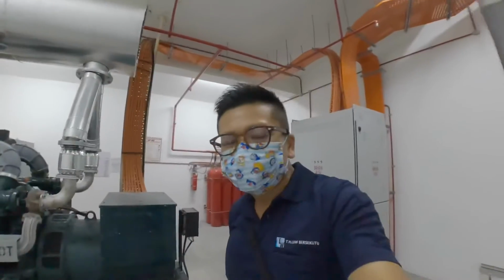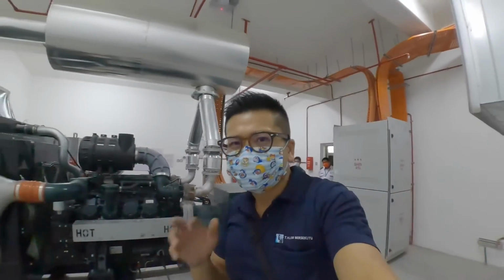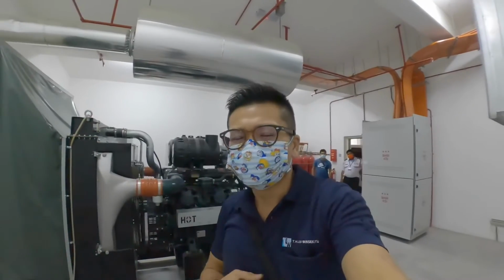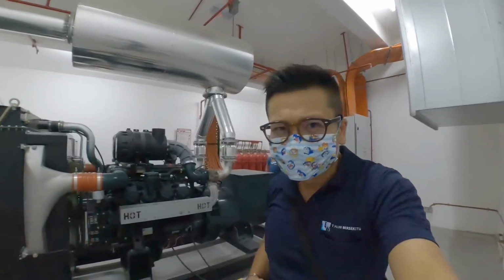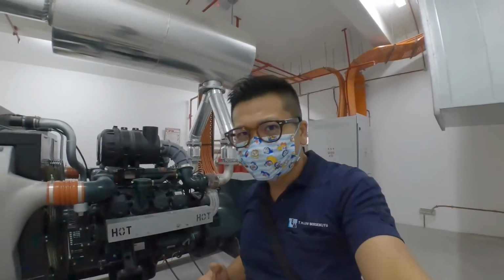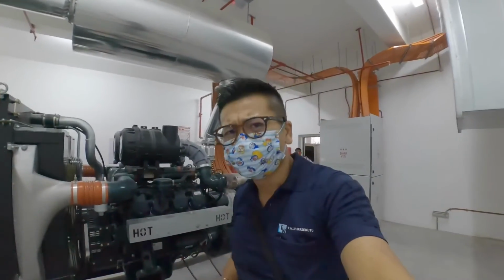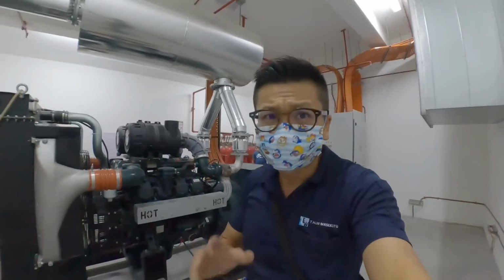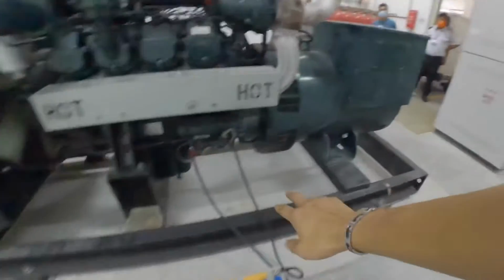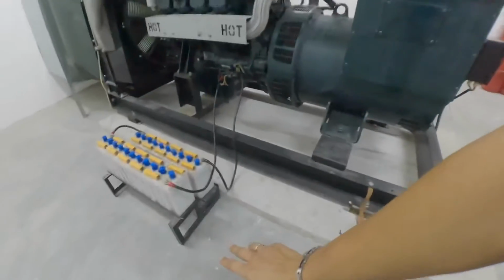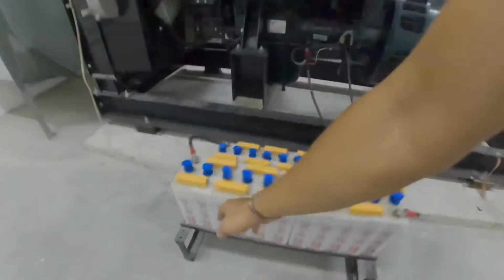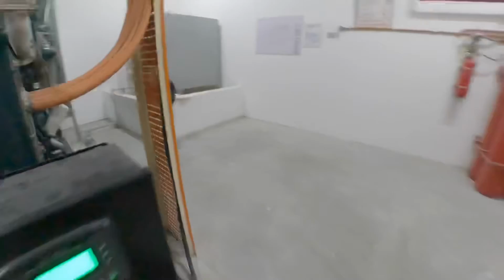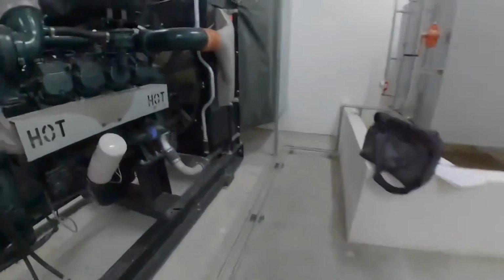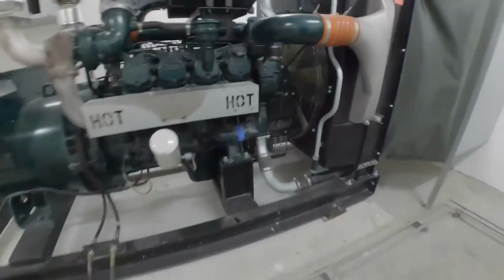Okay, the genset is able to start automatically and stop automatically using the test mode from the genset AMF panel. After start and stop, the genset doesn't show any physical damage or any other problem. So the genset is considered in good condition. There's no leakages after testing of the genset. Everything is in good condition, battery voltage okay. So we are going to test one more time remotely from the genset ATS panel.